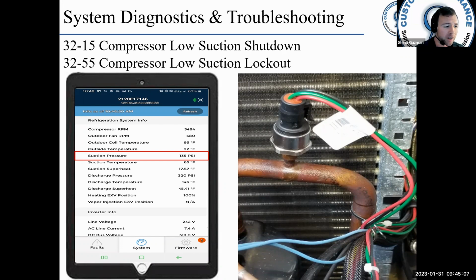What causes low pressure in a system? Okay, blockage in the liquid line filter dryer, stuck TXV, stuck EXV, no airflow or low airflow across the evaporator, low charge, low ambient temperatures. If you're trying to run the system in cooling and it's pretty cool outside, that's going to increase the sensitivity to some of these issues. Remember, the pressures follow each other. So if I've got a low ambient temperature, my head pressure is going to be low. Corresponding suction pressure will be low as well. So that could increase some sensitivity to these lockouts.